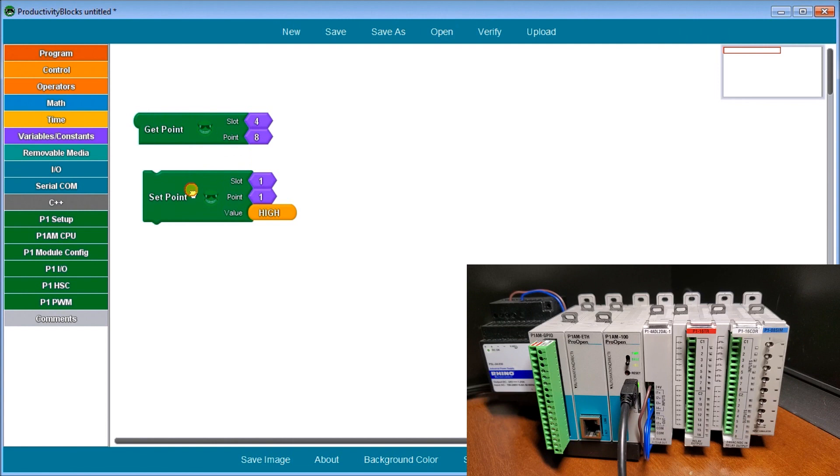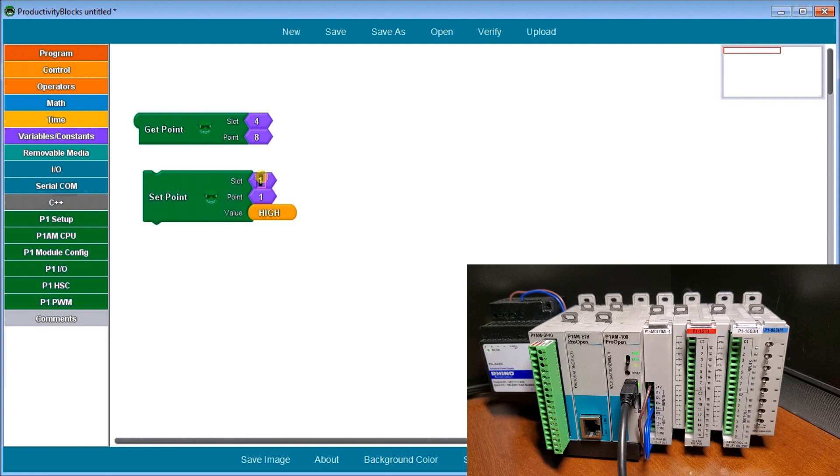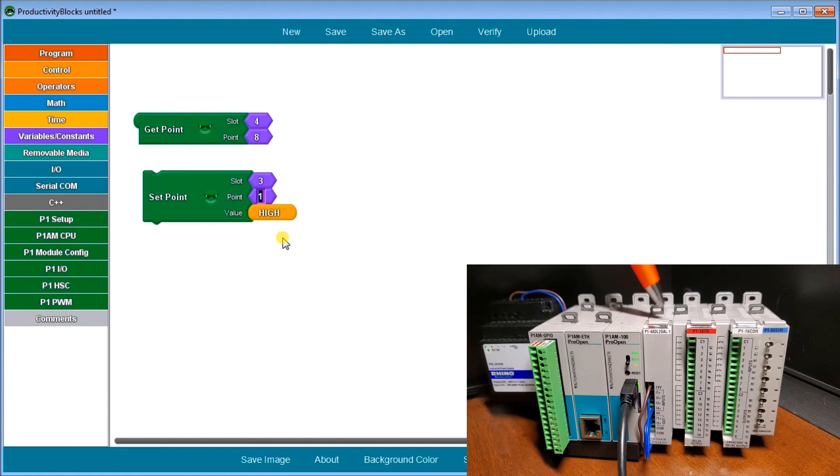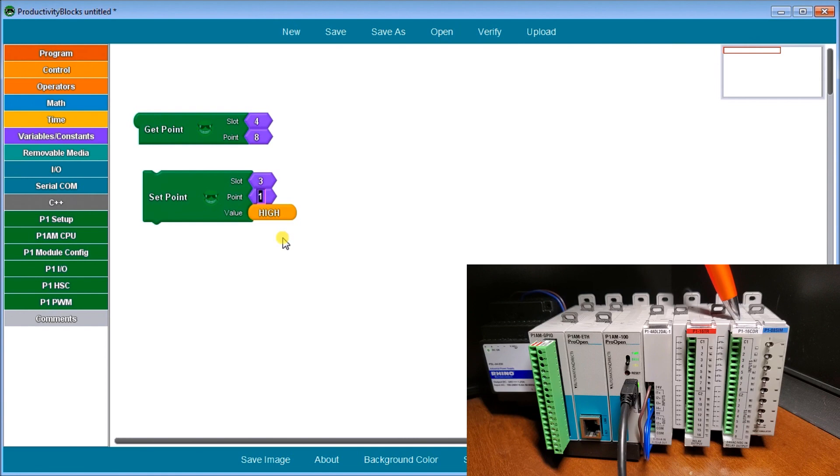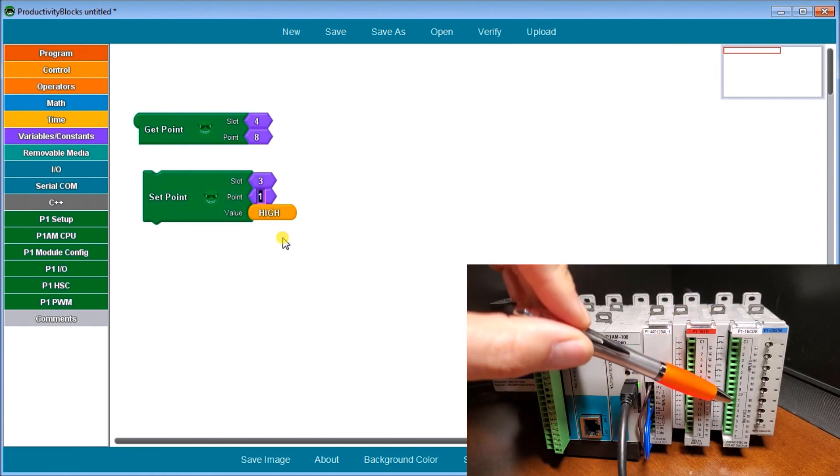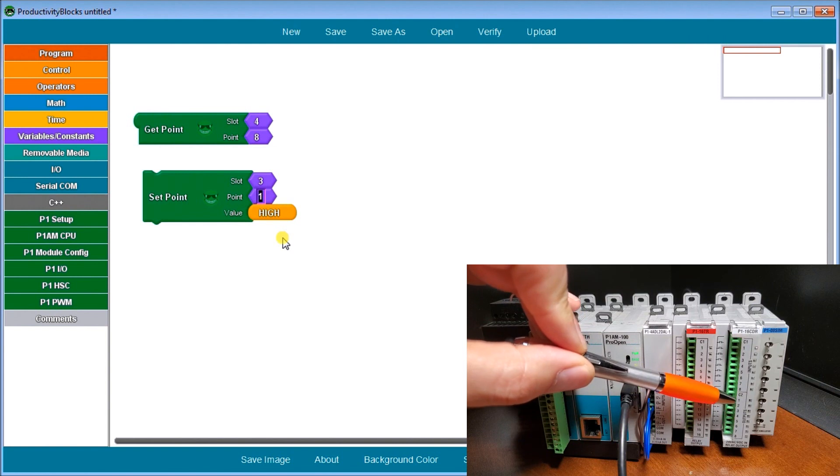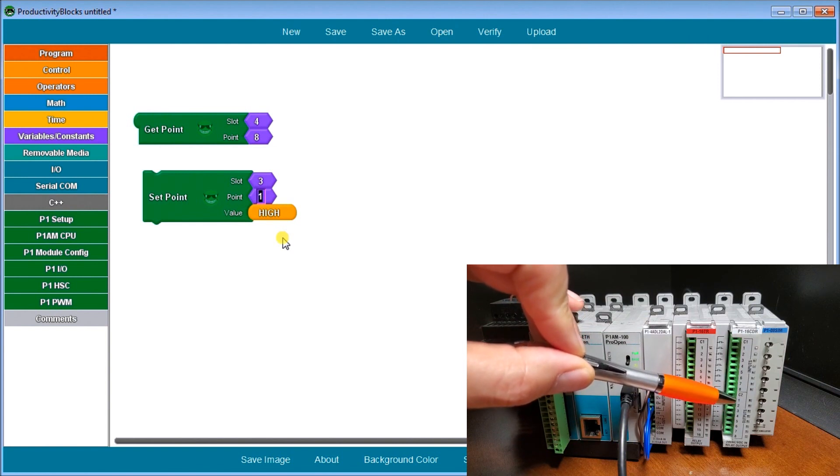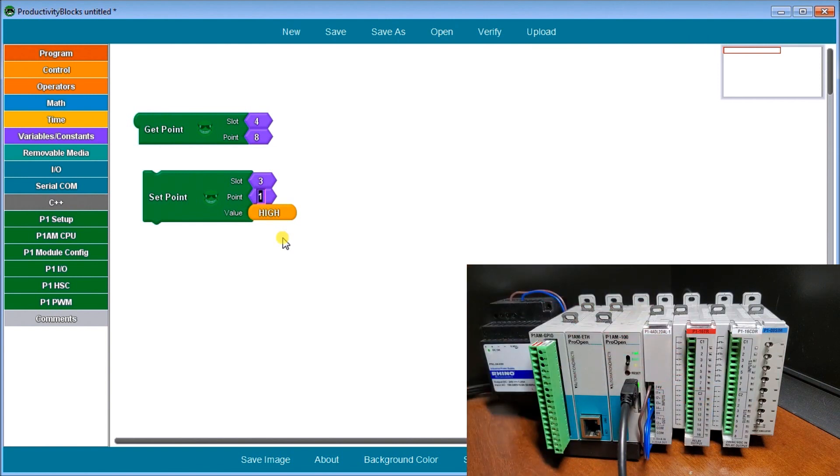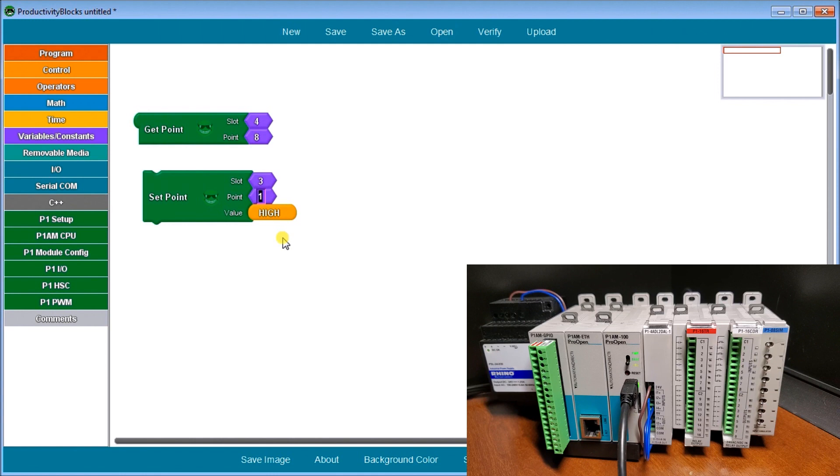Then our set point is controlling one point or one output of our digital output. If we say slot three, point one, and we're going to set it high. Slot three, then point number one. So this will be our first output point which will turn on. That's how we address them and these are the instructions that control the digital I/O.